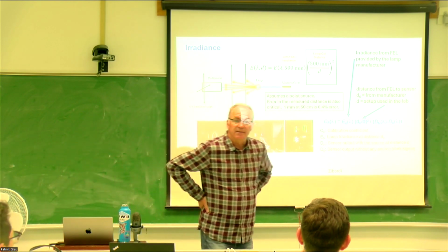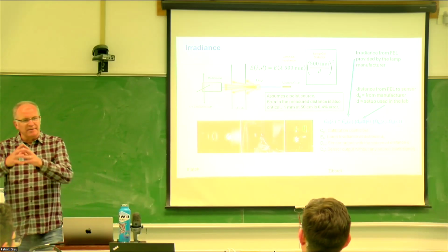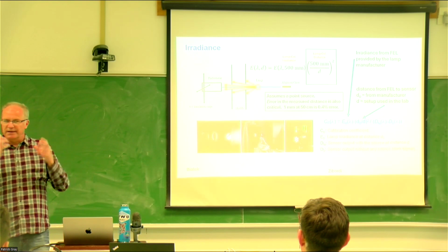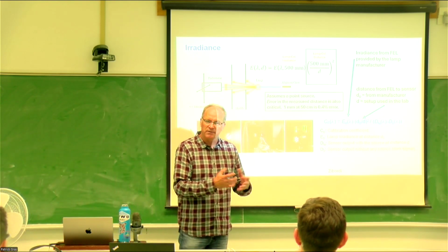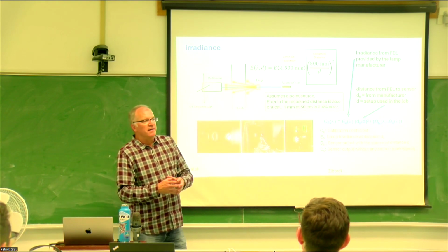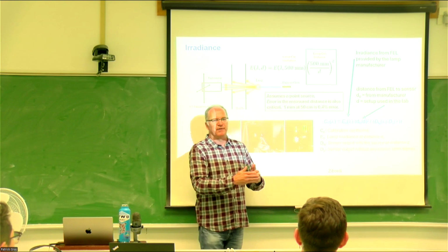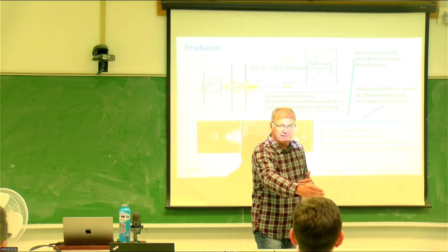Again, because it's NIST traceable. What that means is that there is a chain of custody. So we do this cryogenic calibration that's done against a black body radiation environment. That's why it's cryogenic. Then you get another transfer and say, okay, now I've got this one response. Now, if I use a different light source, how does that measure?